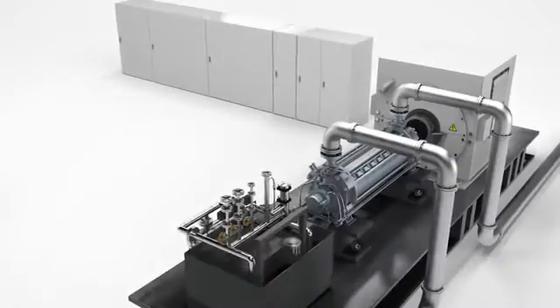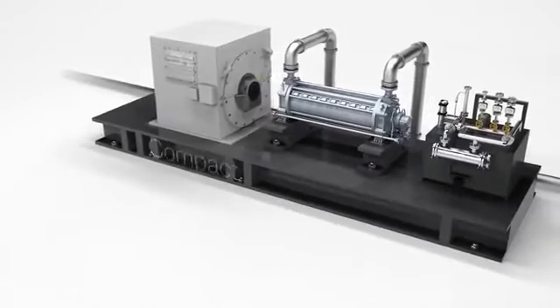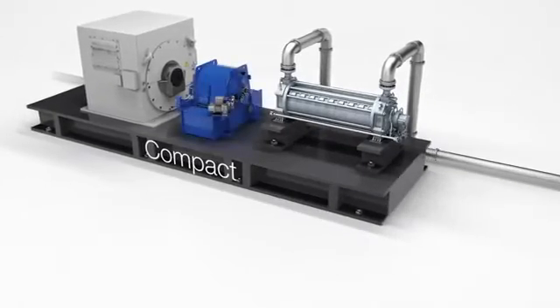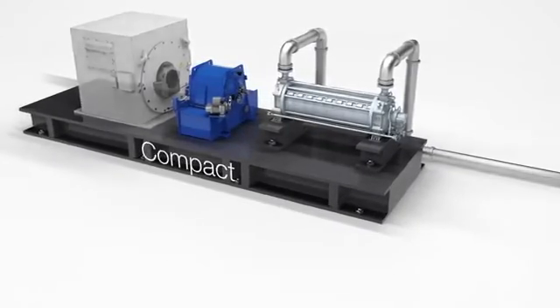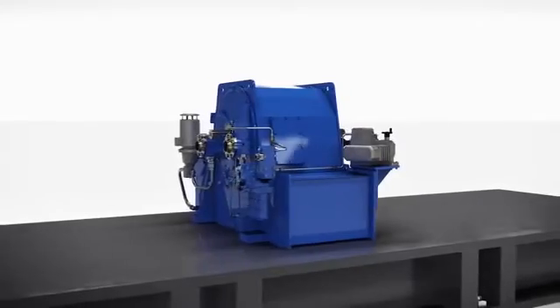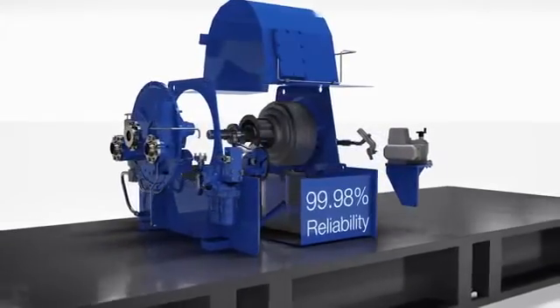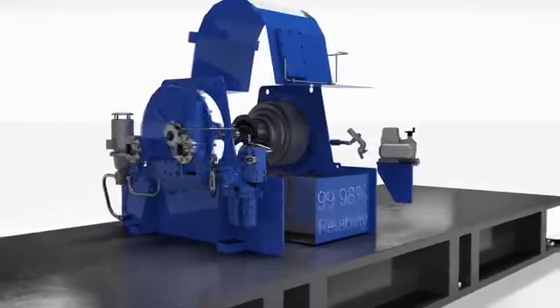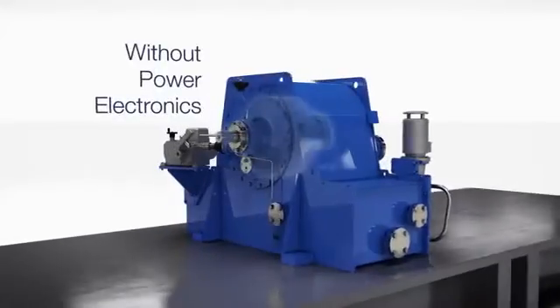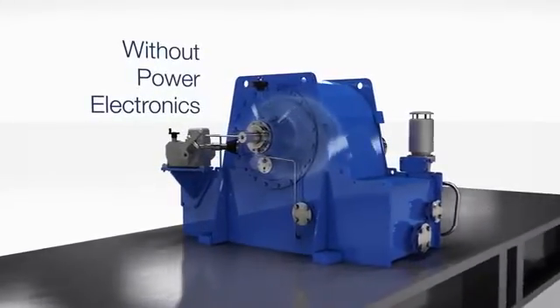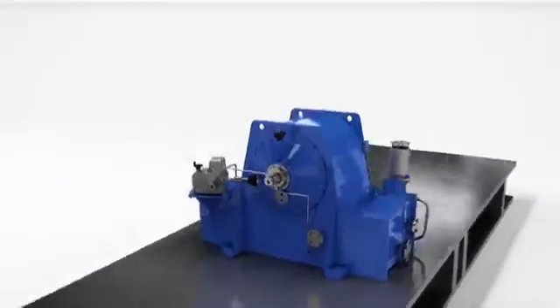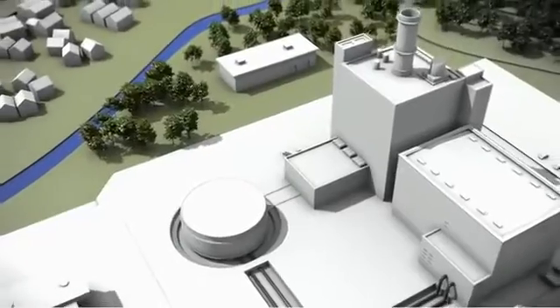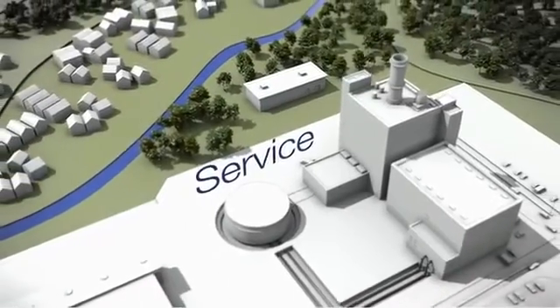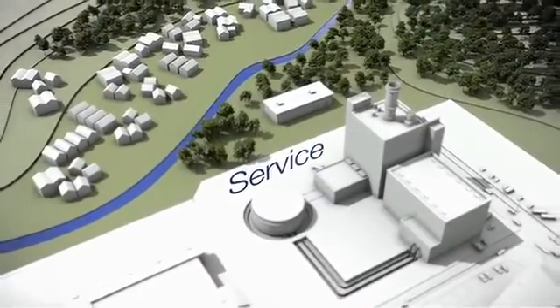Thanks to its compact construction and integrated oil system, the Voith variable speed coupling requires significantly less space than a variable frequency drive. In addition, their unsurpassed reliability makes Voith variable speed couplings a convincing choice. They require no power electronics, for which there are usually no spare parts available after just a few years. Voith guarantees replacement part availability for the entire service life cycle, with service available anywhere in the world.